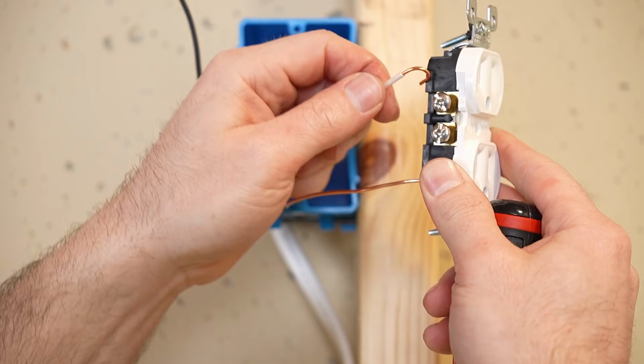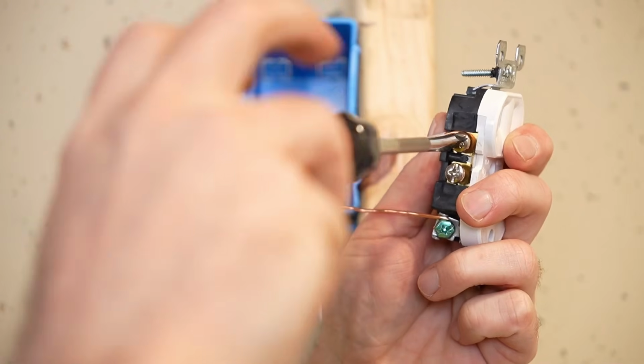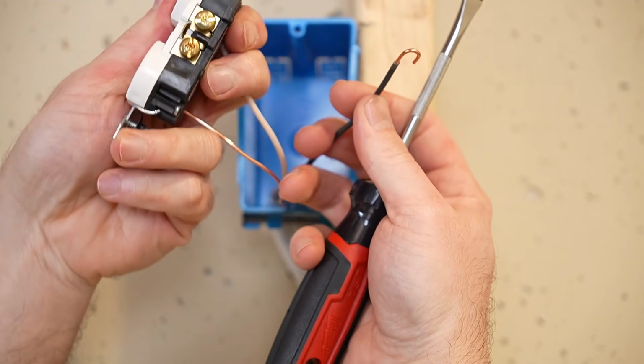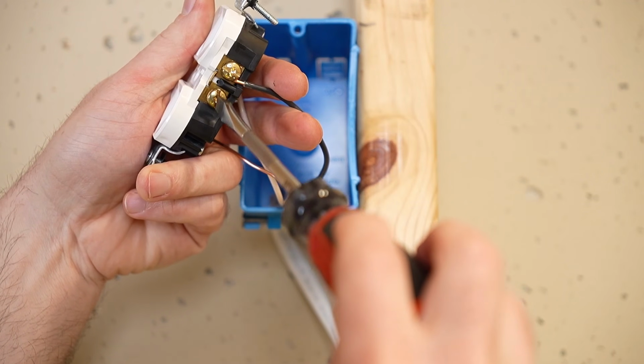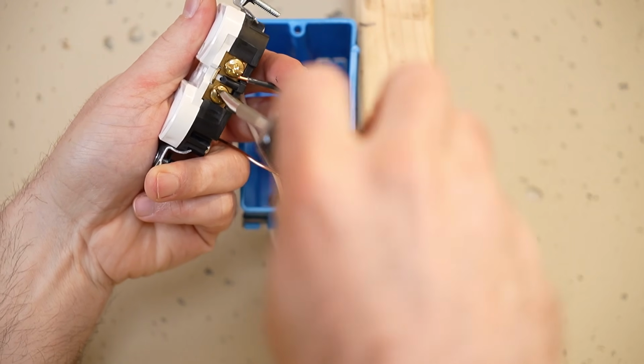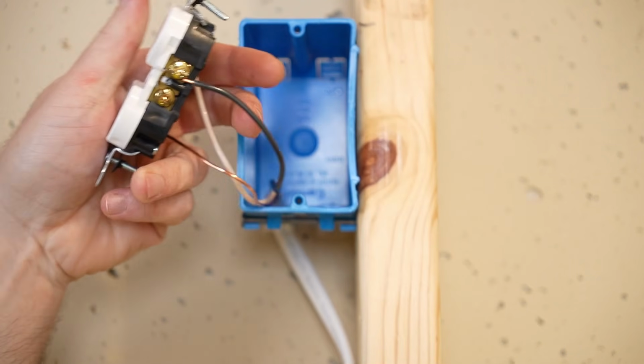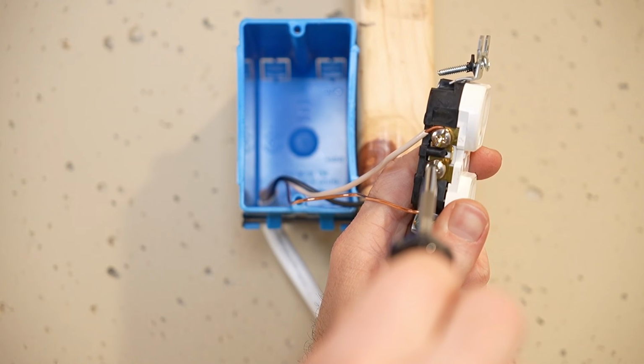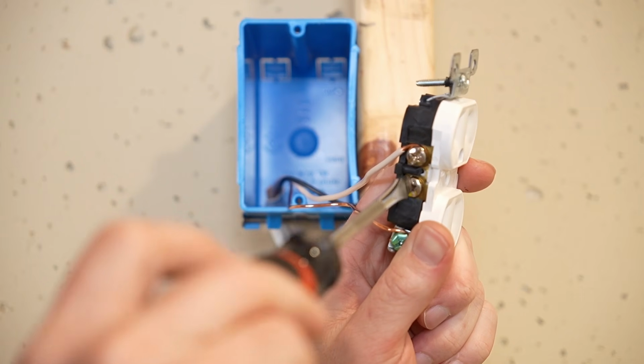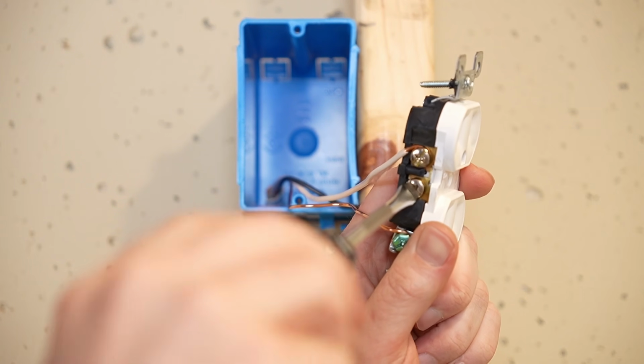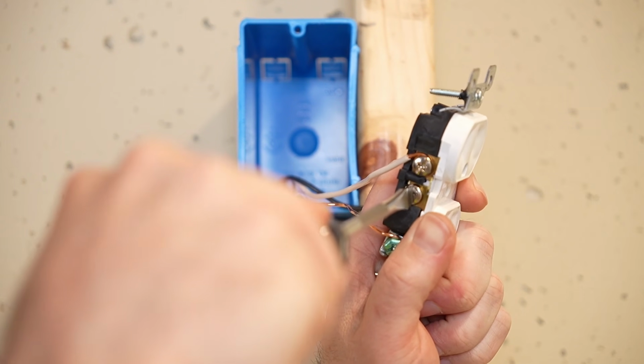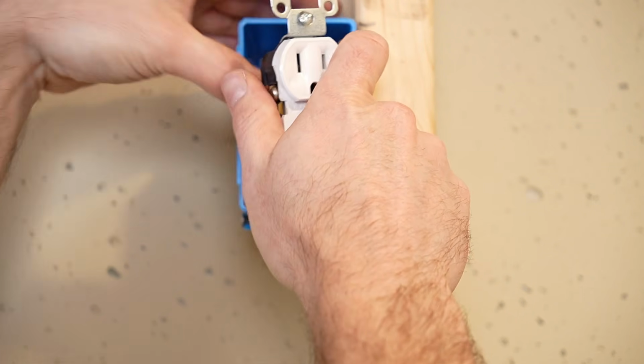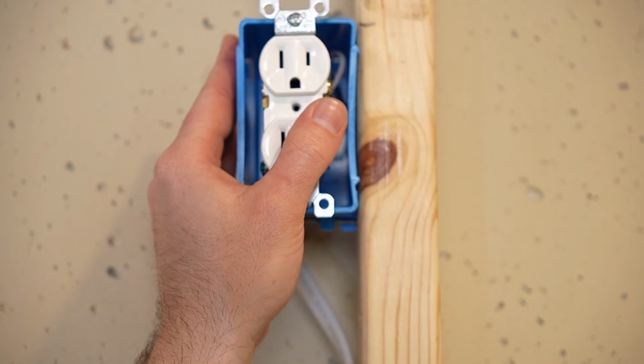Silver terminal is our neutral. And lastly, the gold terminal is our hot. And let's tighten up those extra screws that aren't used. That way we reduce the chance of a short circuit within the box. Same for that neutral. If the ground were to touch the neutral, that would create what's called a ground fault, which may be the topic of a future video. Now we can fold our wires up into the box and mount the receptacle.